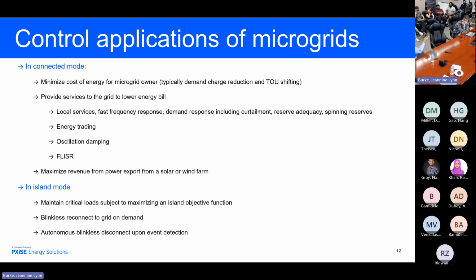So the utility wants to serve the maximum number of loads. That makes the maximum amount of money. So they want to disconnect the minimum number of guys to keep the grid stable, because if they don't disconnect them, the rest of the grid is going to collapse and they're going to lose a lot of revenue. So it's purely a greedy solution. Now in island mode, I want to be able to solve a different objective function. I want to maximize the time to live typically. And finally, when I do disconnect and reconnect, I want to do that seamlessly.